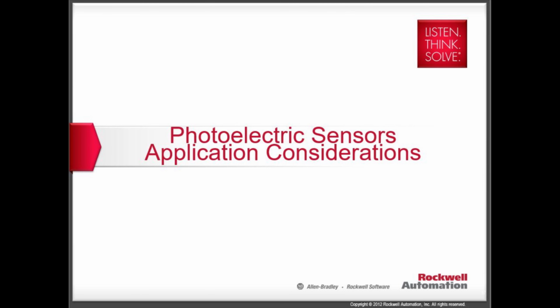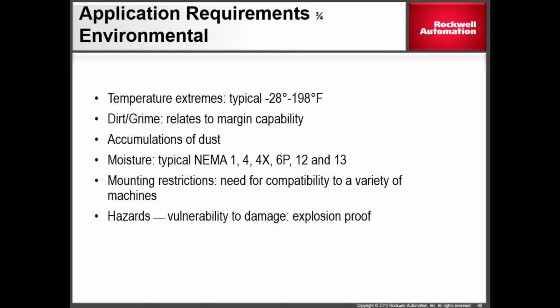Let's talk briefly about application considerations for photoelectric sensors. Some of the things you might want to consider, or actually need to consider, when you're looking at a photosensor: temperature extremes. Are you in a real cold environment or a real hot environment? Most of the sensors have a temperature rating. You have to make sure that it meets the requirement of the area you're trying to put it in.